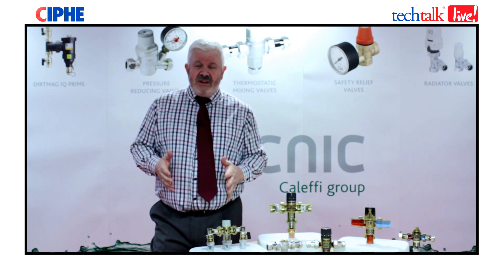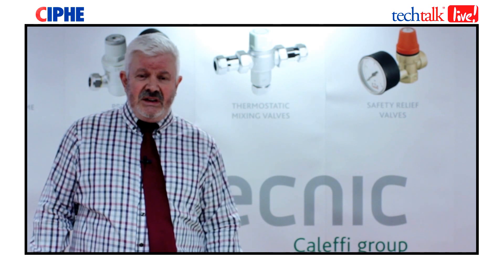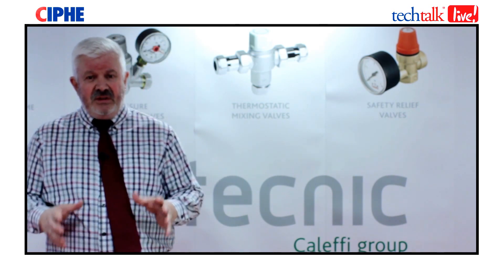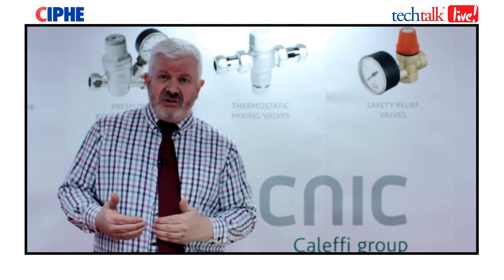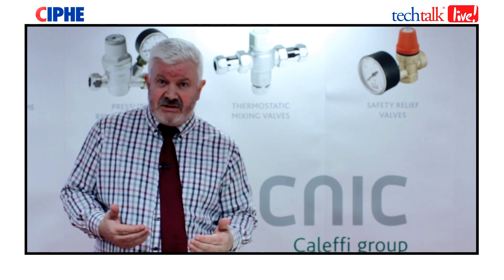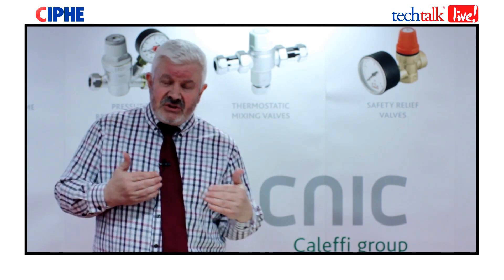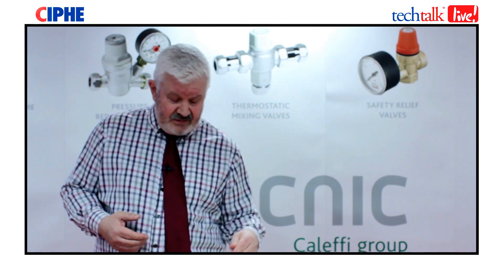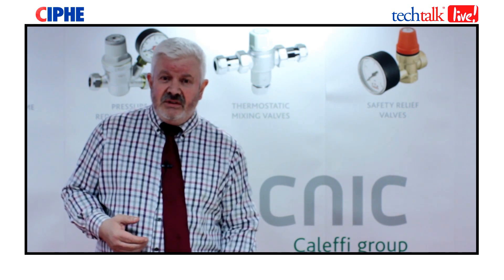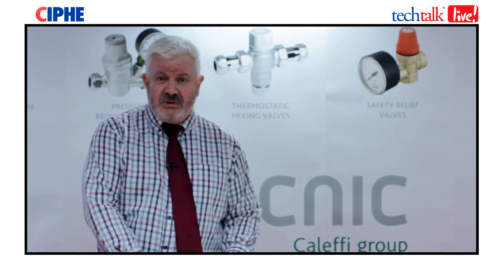A TMV3 is an enhanced specification. Prior to installing a TMV, the system should be thoroughly cleaned and flushed. TMV2s and TMV3s fall into two different categories: 2-in-1 and 4-in-1. A TMV that is a 4-in-1 has a check valve, a strainer, an isolating valve and a test port.